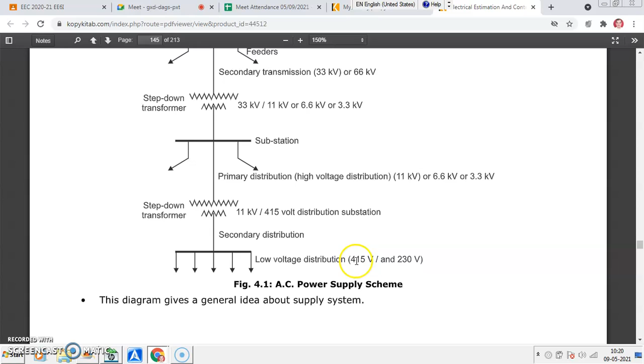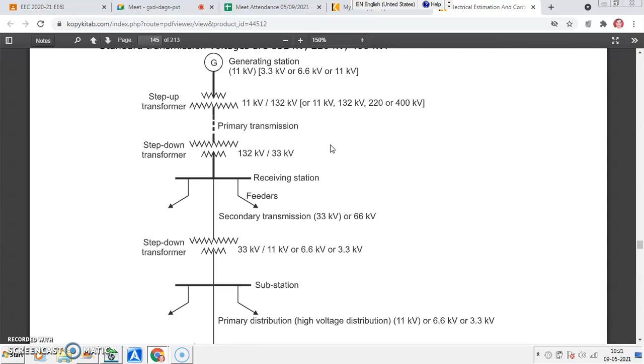For HT consumer level, you have the distribution of either 11 kV or 22 kV. These HT consumers directly have a substation in their premises, and they have their own distribution system inside their premises. So these bulk consumers are fed with 11 kV or 22 kV. Retail consumers, the domestic consumers like we have, or agricultural consumers, are fed at a very low voltage level, that is 415 volt 3 phase AC or single phase 230 volt AC. So this is in general our distribution system, right from generation to transmission.